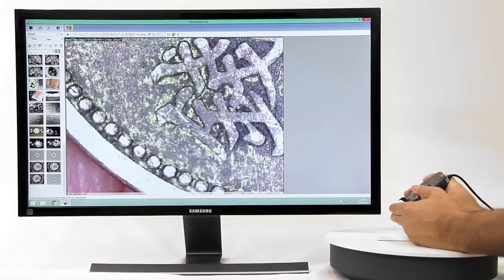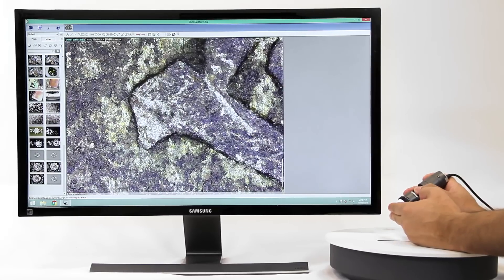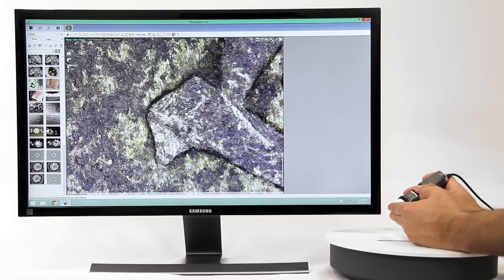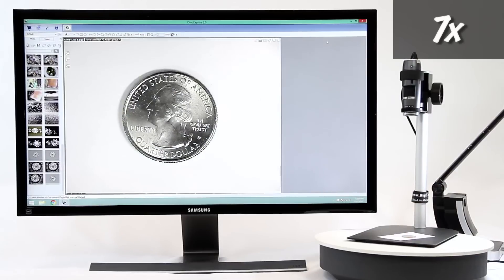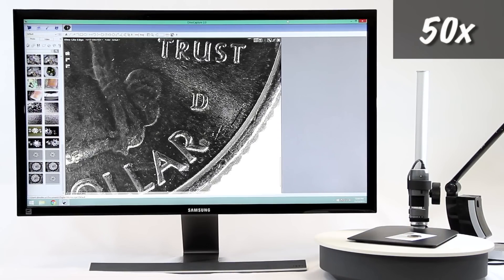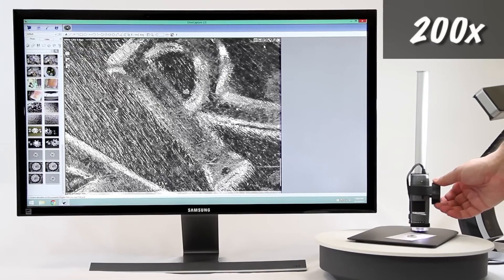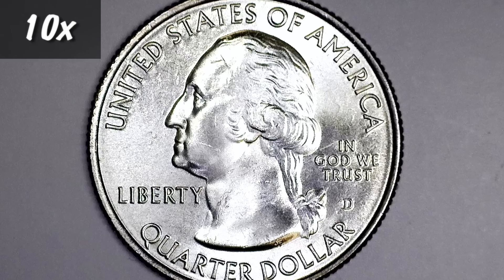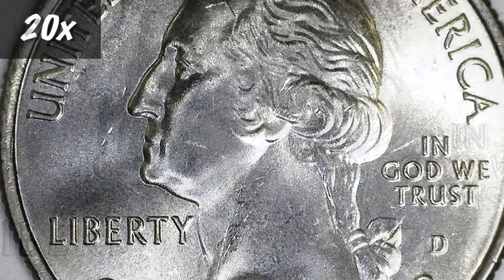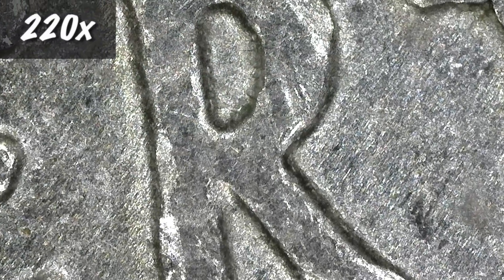The DinoLite is a handheld microscope camera with most standard models going up to 220x magnification. For lower magnifications, move away from the object and lower the magnification on the dial. For higher magnifications, adjust the dial and move closer to the object. Lower magnifications will have a larger field of view and higher magnifications will be closer with less field of view.